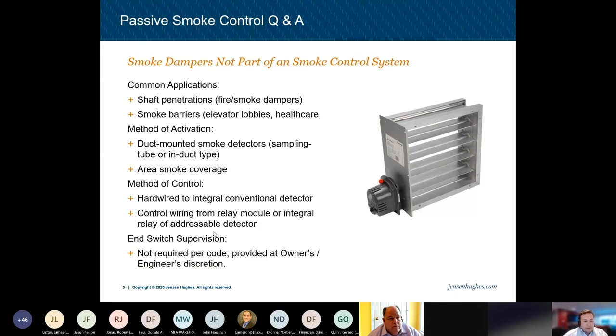The method of actuation is typically through duct-mounted detectors or area coverage. You could have sampling tube type or in duct type, or you could have 100% area coverage provided throughout the space served by the associated penetration. The method of control, how these are typically actuated, they can either be hardwired to an integral conventional detector that's wired and factory mounted by the damper manufacturer, or you could have control wiring from a relay module, standalone relay, or an integral relay of addressable detector.